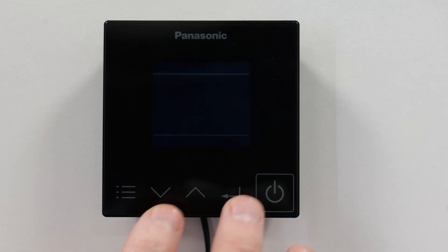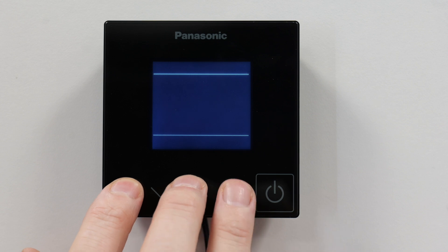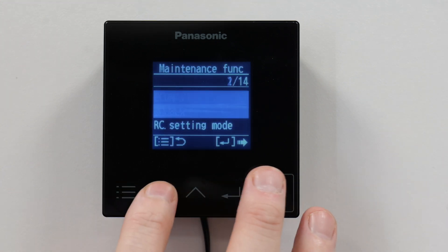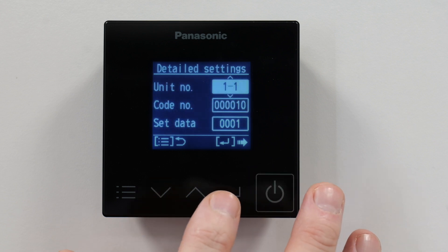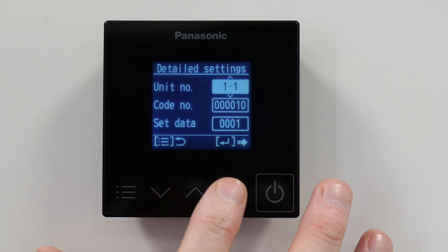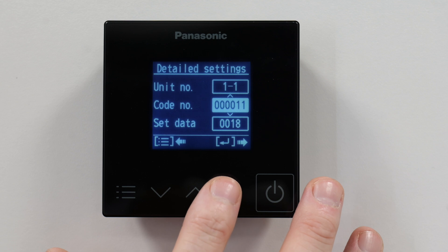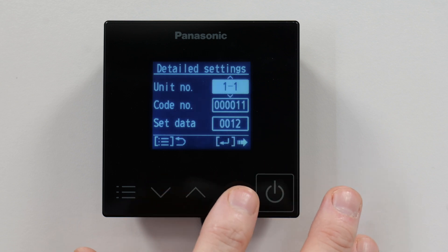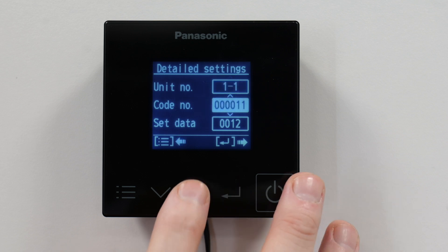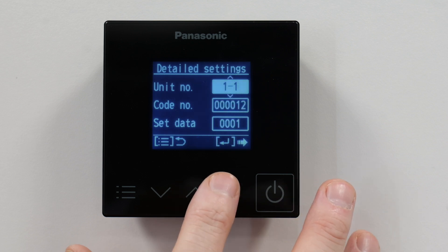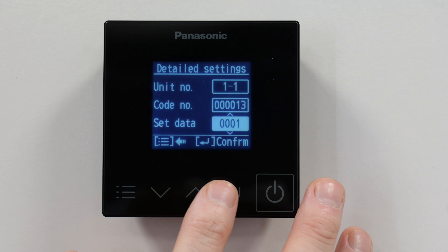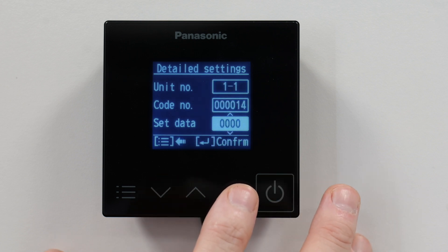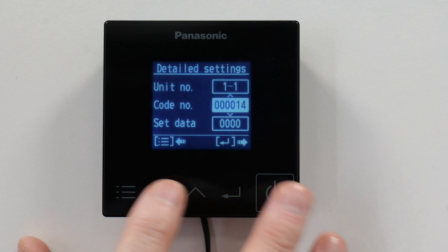Once we're back in, we go back into the maintenance function menu using the three buttons and we're going to set the address settings in detailed settings. The first code we change is code 11 — this is the capacity setting and this needs to be the same as the indoor unit. Then code 12 is the outdoor address, set to 1. Code 13 is the indoor address, set to 1. And code 14 is the controller, which is set to four zeros.